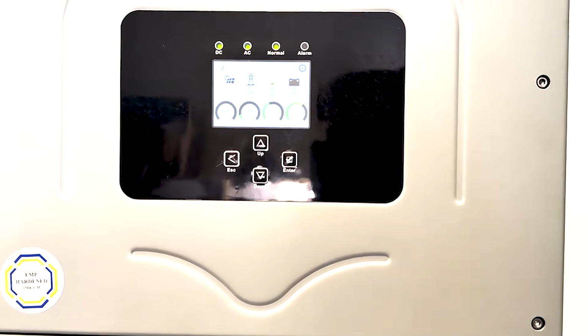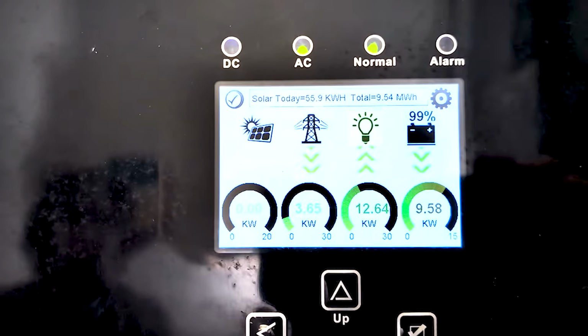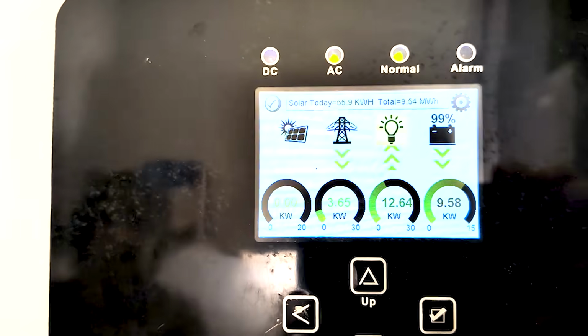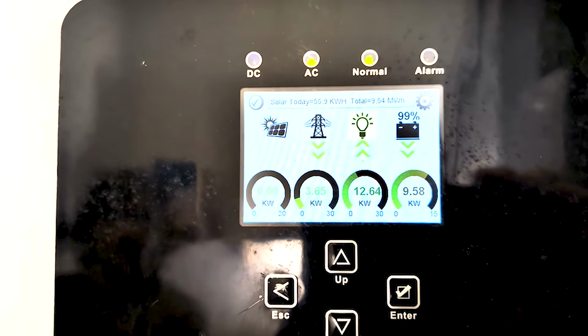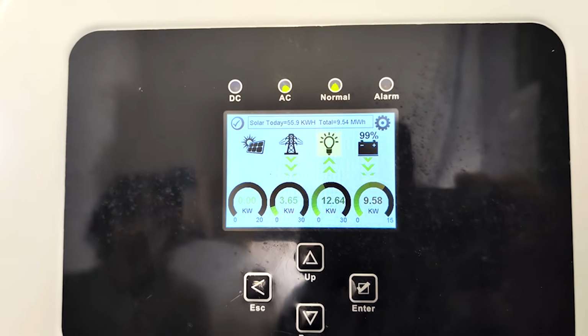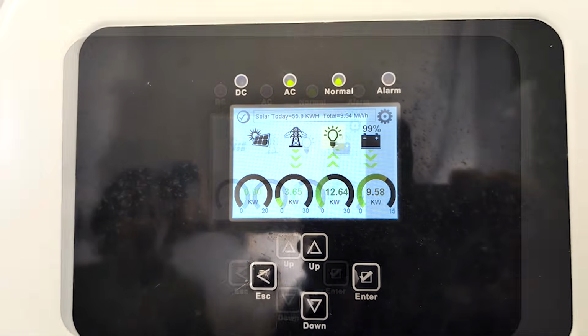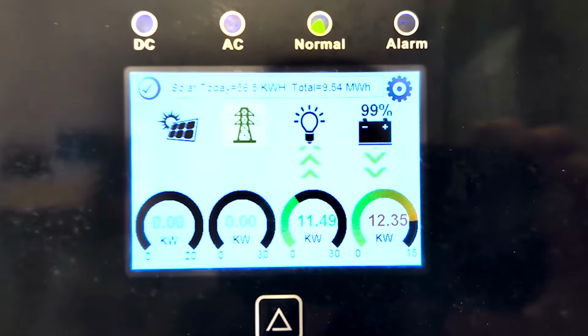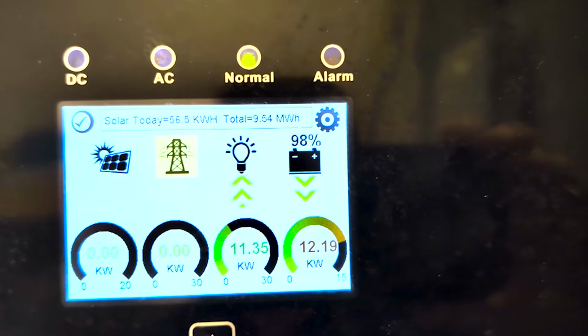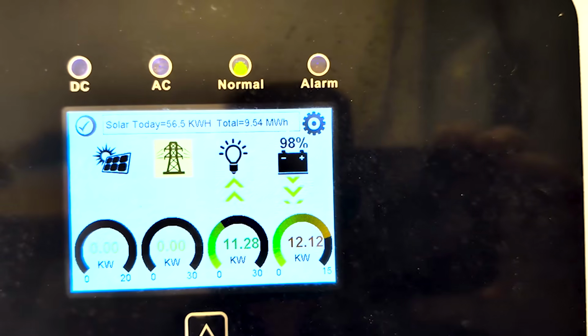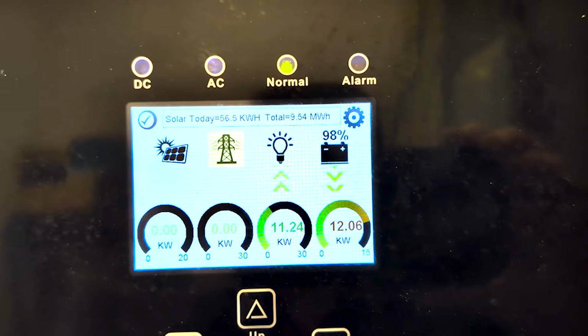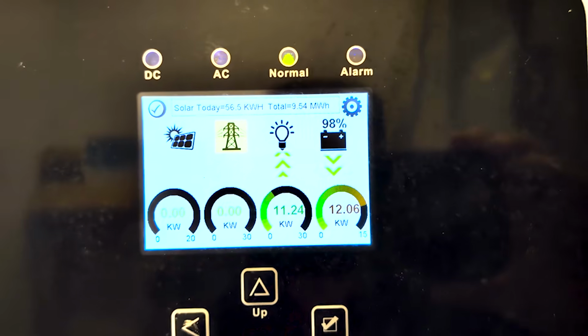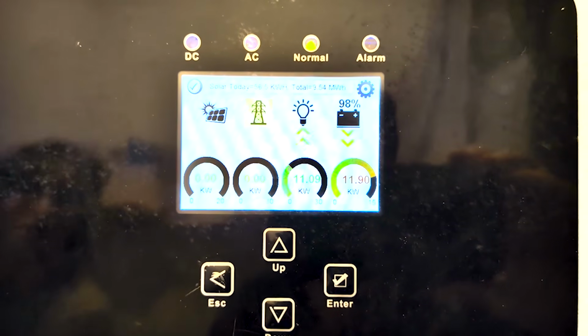It's 1:30, we're starting our test, running a 12.6 kW load with no solar on a 15K. It's pulling from the grid. We've got to go turn the grid off. Okay, it's torture testing time. We got 12.35, whatever. We turn the grid off, we turn the solar off. It's only battery and Sol-Ark now.